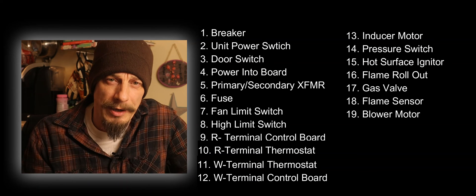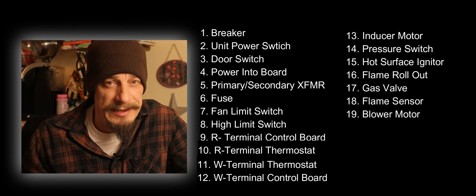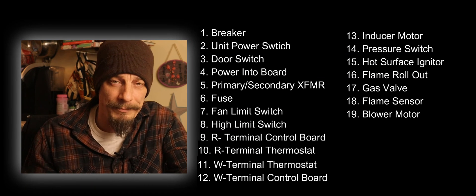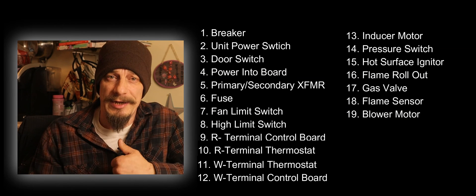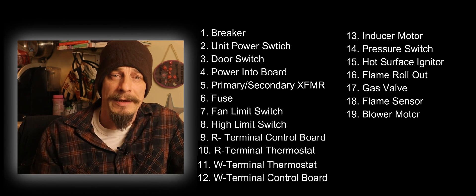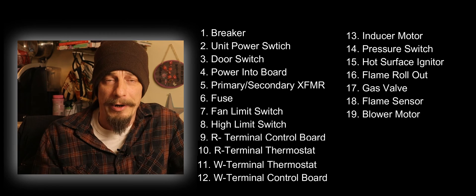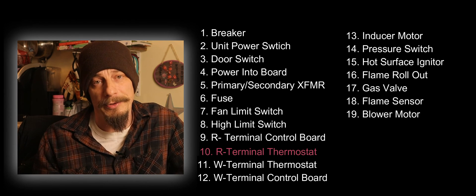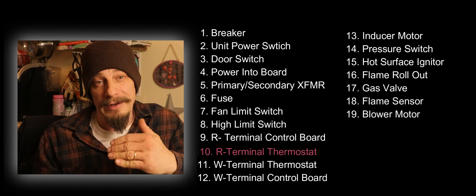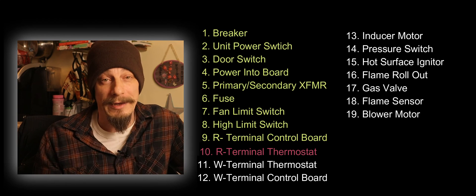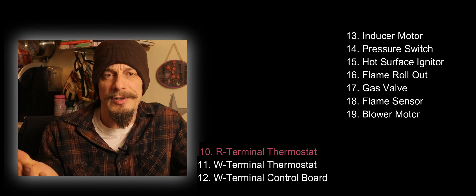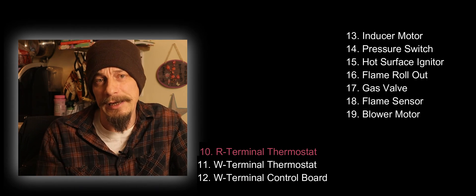We're going out on a no heating call and the customer says they put the heat on at the thermostat and absolutely nothing happens. You walk up to the thermostat, you verify there's heat, you take the thermostat off the wall and you check for power at your R terminal and you have power at your R terminal. What does this mean? If you look at the list, if you have power at the R terminal at your thermostat, everything before that is probably working just fine so you can eliminate everything off that list.